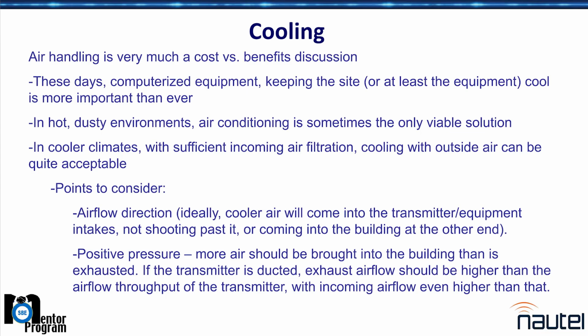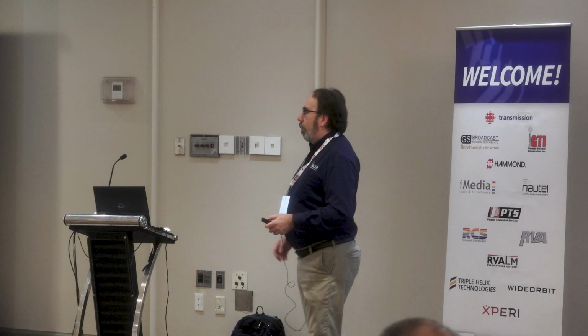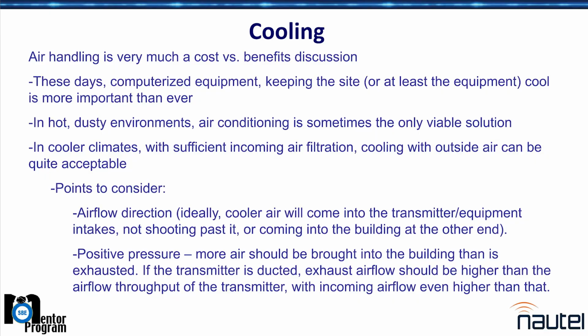Two things I notice about cooling: there's almost never enough of it going through the equipment. I've walked into rooms where the air was blowing through the room at 100 miles an hour, right behind the gear and sucking all the air away from the transmitter. So the air has got to go through the equipment, not around it or over it.